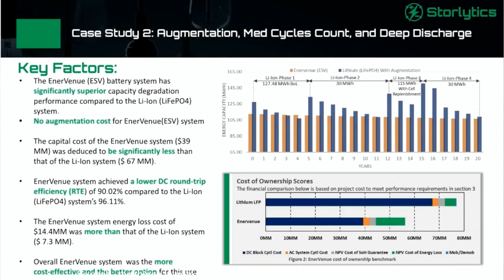So one of the things to note here is that the EnerVenue system did not require any augmentations, compared to lithium which needed multiple cycles of augmentation. We see the impact of that on the overall cost. The overall cost was around 39 million for EnerVenue, but for lithium there was an initial capex cost and then there was an augmentation cost as well. So all this together was coming out to be more than what EnerVenue had.